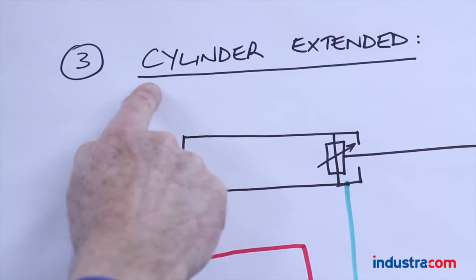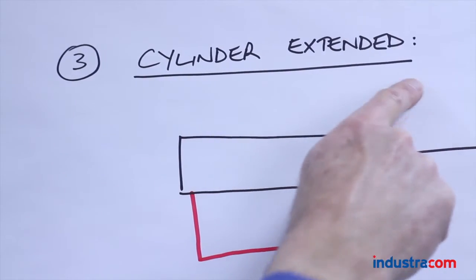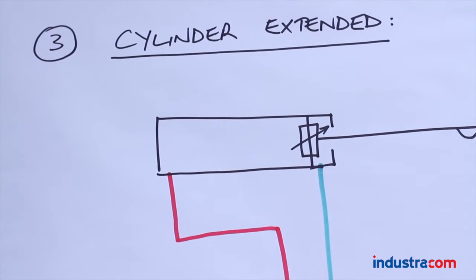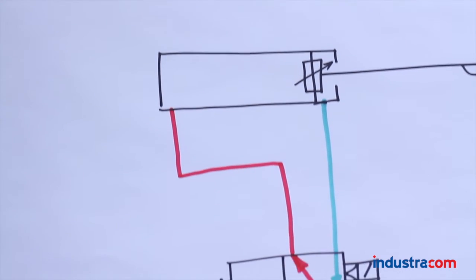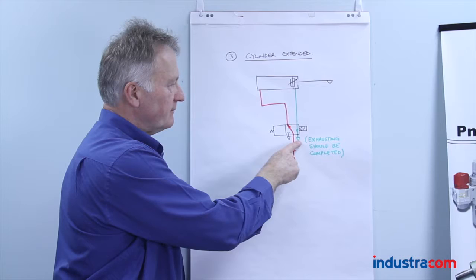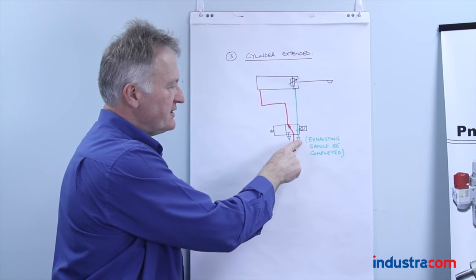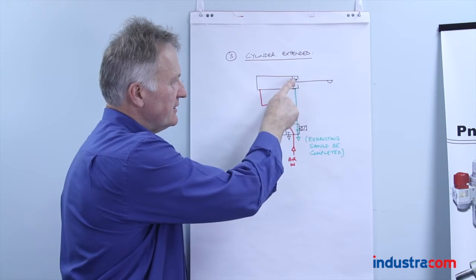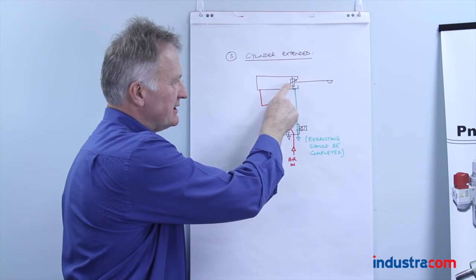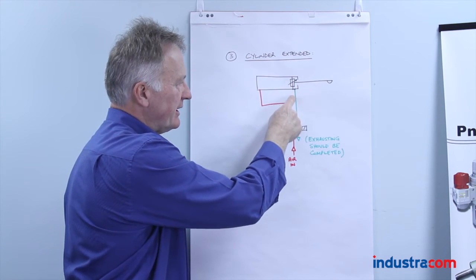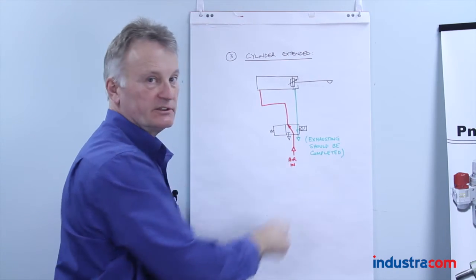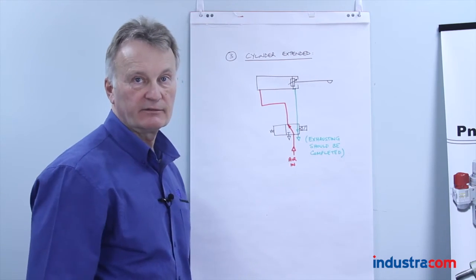Once the cylinder has extended, there should now be no air exhausting out through the exhaust port of the valve. If there is air exhausting out of here, it's because the actuator is leaking — we're getting bypass — and it continues to exhaust out of the valve.